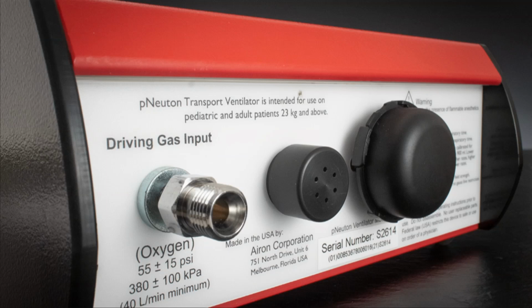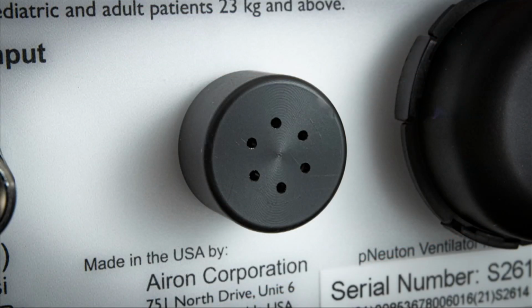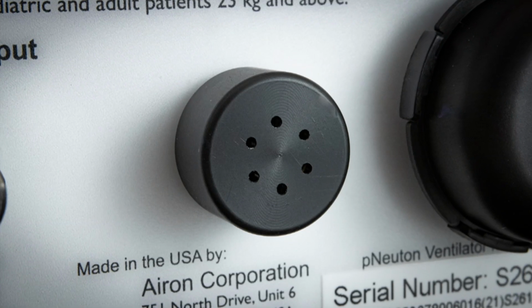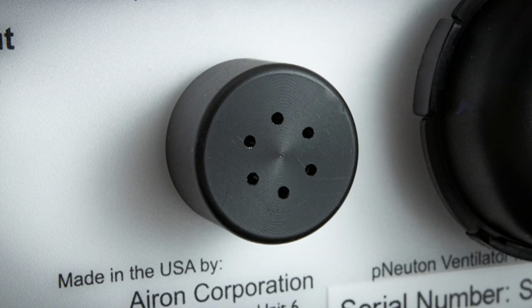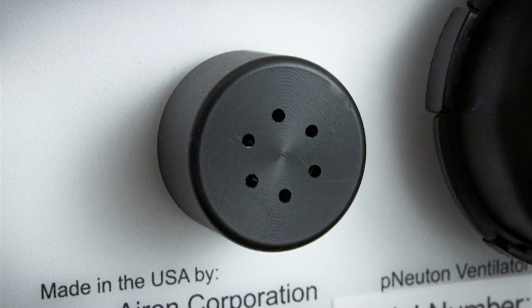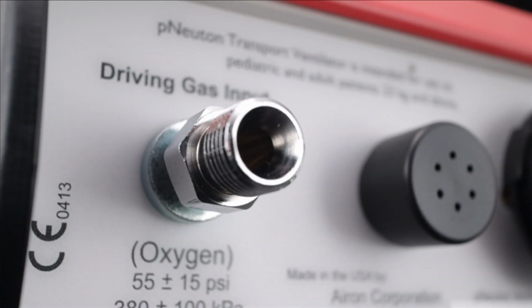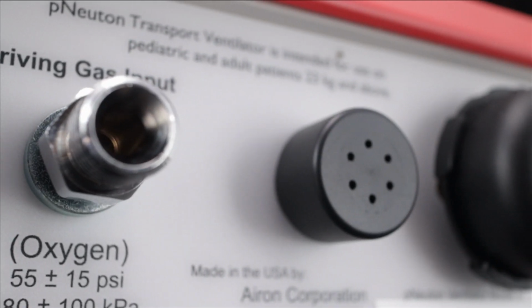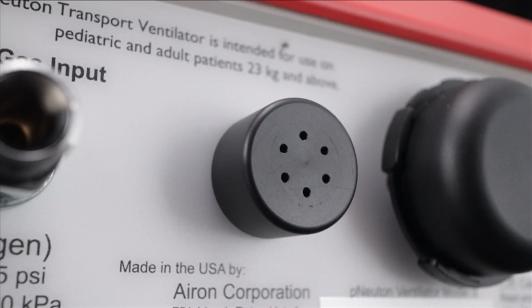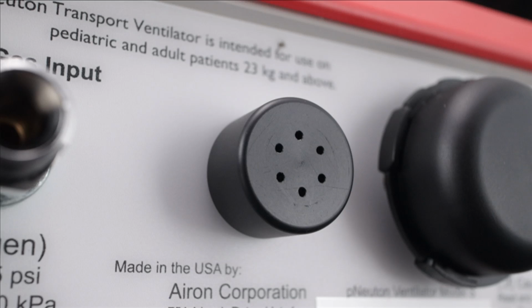Audible alarms. The next item is the audible alarm. The alarm sound comes out of this circle of holes on the adapter. Please be sure to never put anything in these holes or cover them up, otherwise the alarm will not be audible. The alarm will sound when the oxygen source gas pressure drops below 30 psi. The ventilator will continue to operate as long as oxygen is available.